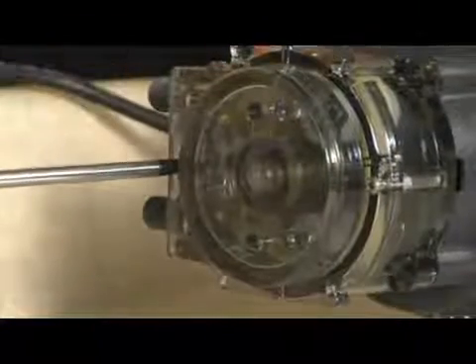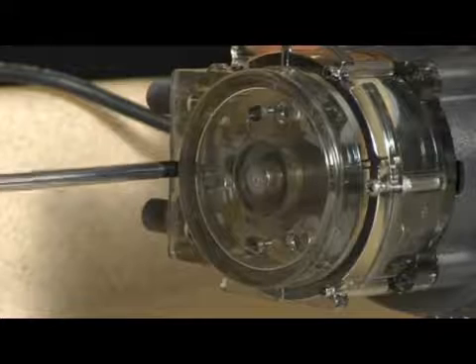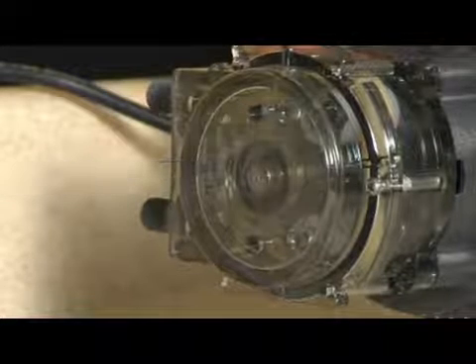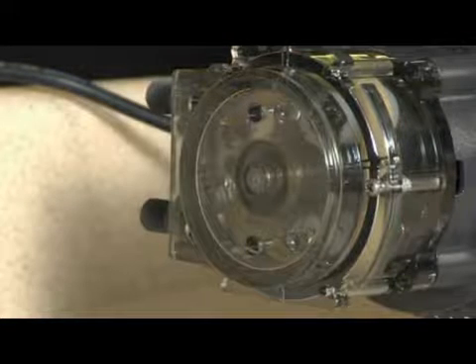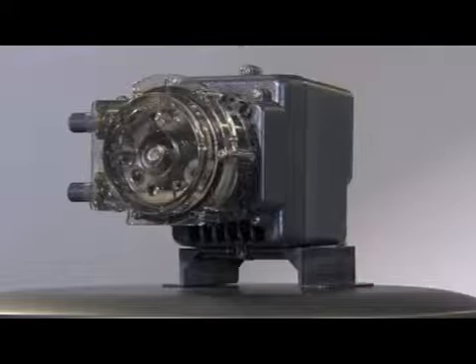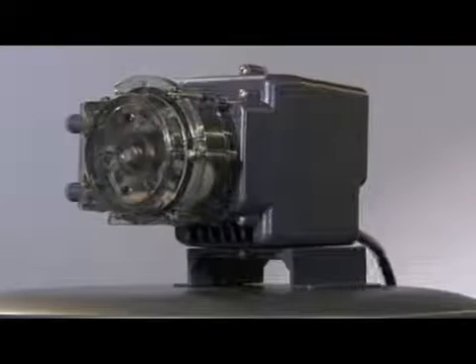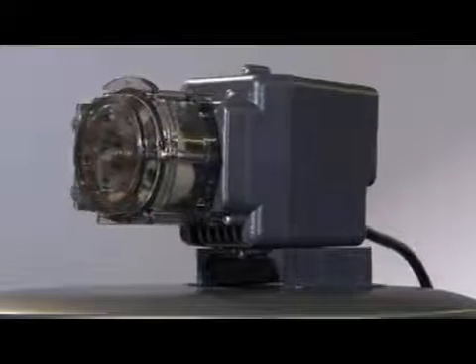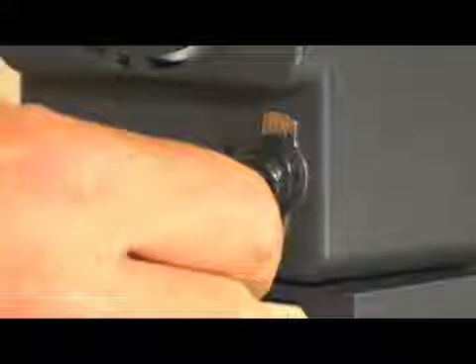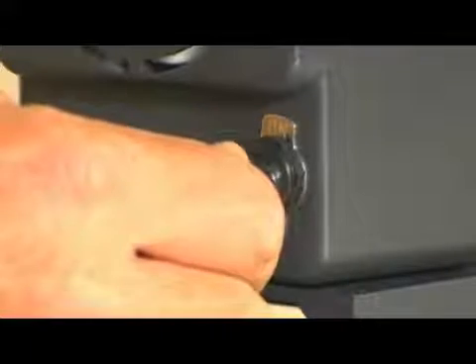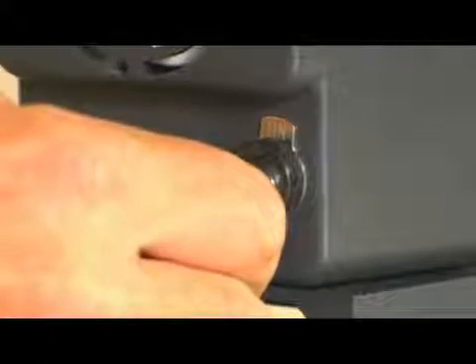Tighten the cover screws finger tight only. The cover is not on securely if there is a gap between the screw boss and the cover. To install a new tube in the Classic Series fixed output pump, follow the instructions for the adjustable pump and utilize the on-off switch to jog the roller assembly in the absence of the feed rate control.